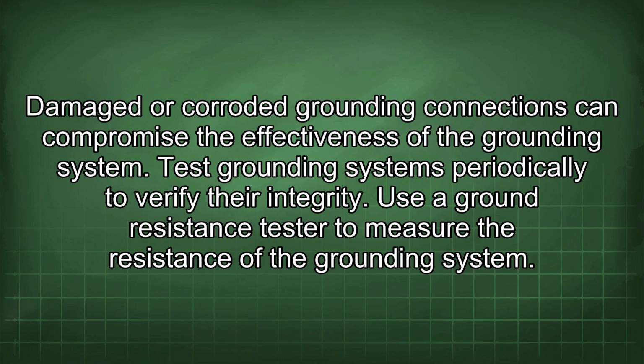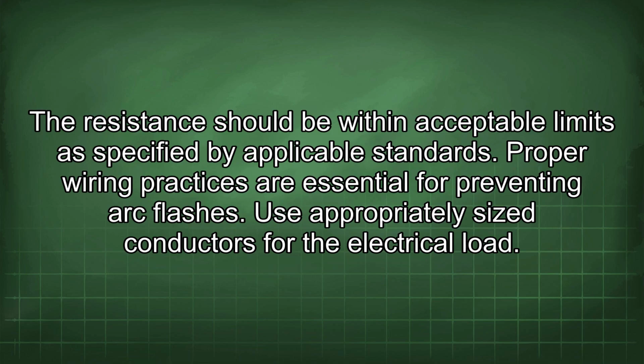Use a ground resistance tester to measure the resistance of the grounding system. The resistance should be within acceptable limits as specified by applicable standards. Proper wiring practices are essential for preventing arc flashes.